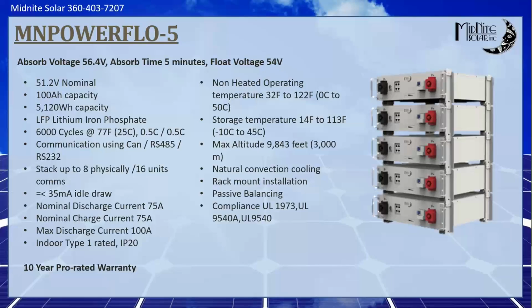So 9540A is an interesting one. We get asked from time to time for the certification for that. You actually don't get one. 9540A is not a testing that you get certification for. It's a test requirement for 9540. It's kind of a really weird scenario, but the testing laboratory, UL, ETL, SGS, whoever it may be, will test to 9540A and give you a UL 9540 listing. There are some exceptions to that where you can not do the full 9540A, but you have to put that very clearly on your labeling that you got an exception to 9540.